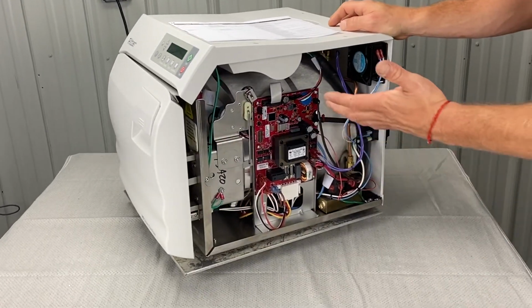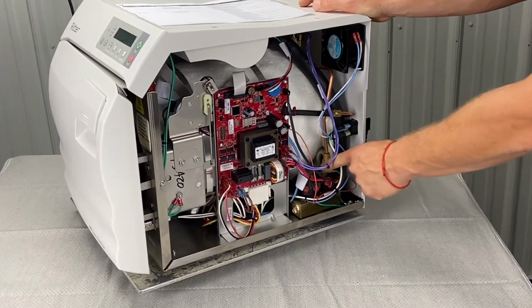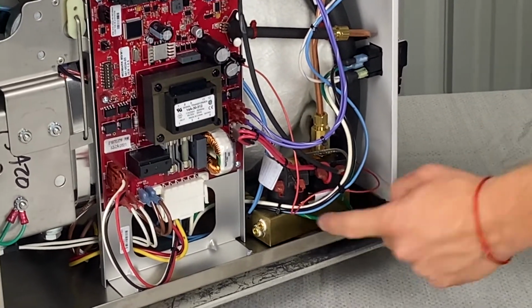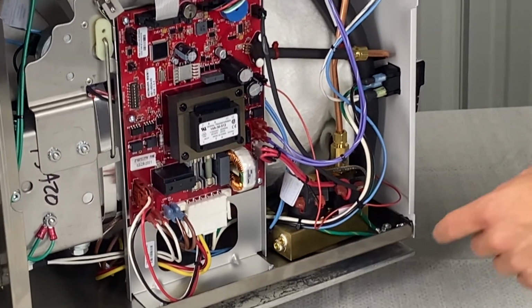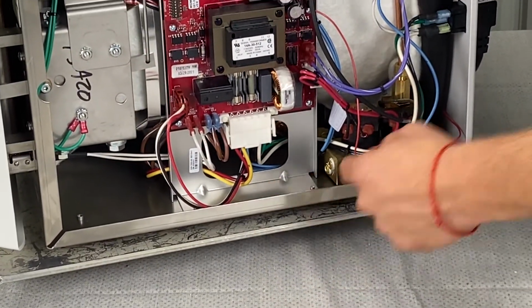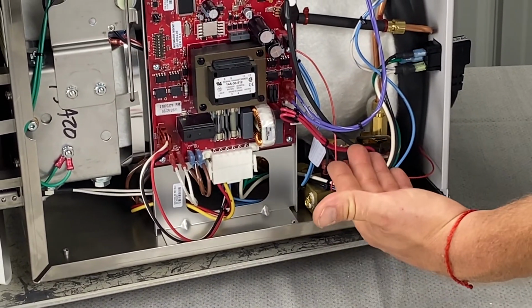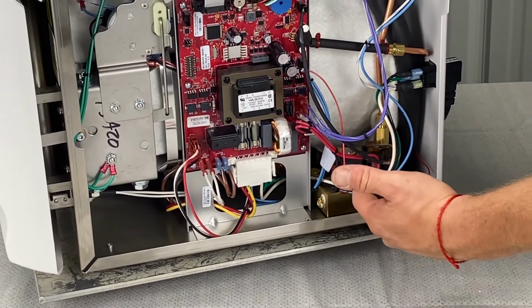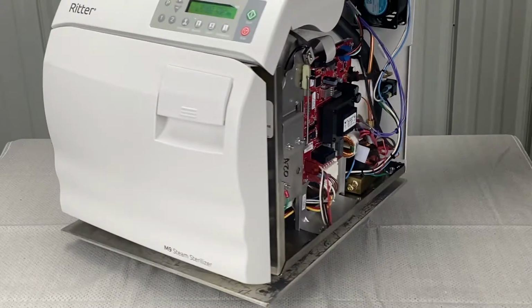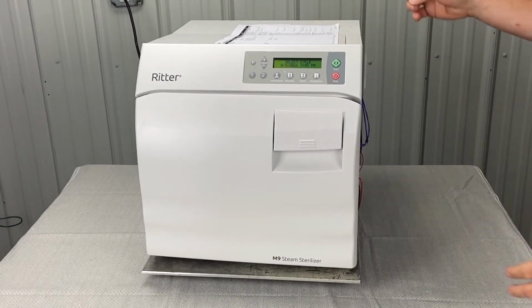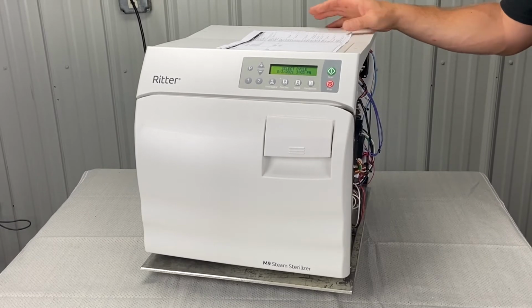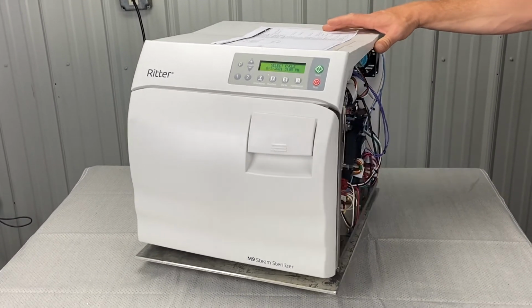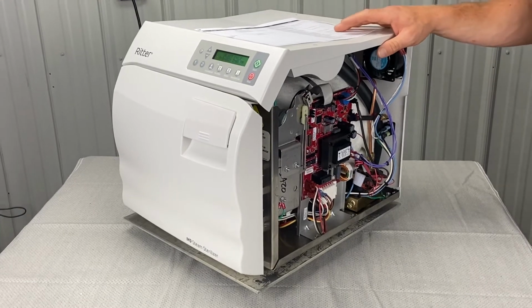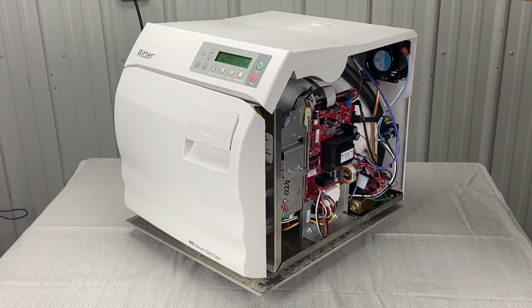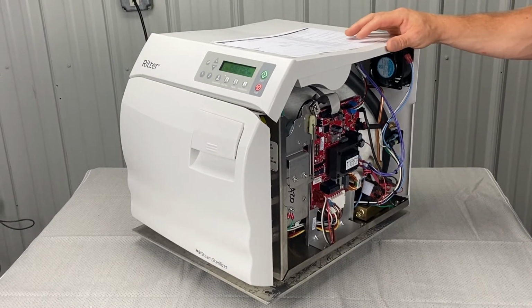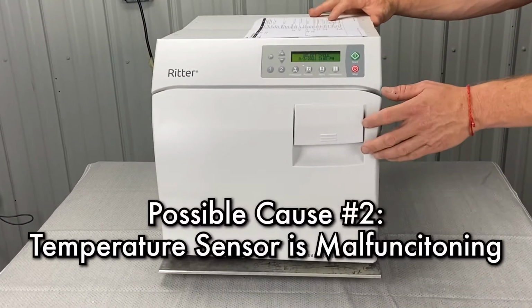So it's really nice, like I said, to run this with the cover off, because now we can inspect these valves. You might see leaks come out from underneath here where they screw it to the manifold. You can look underneath. You might see leaking coming from the heating element area. There's gaskets there that go bad over time. There's plumbing under there that goes bad over time, or loosens up as this thing gets hot and vents and whatever. So you're going to check all the fittings, tighten or replace the fittings if necessary. Usually you can just throw whatever size wrench on it, tighten it up a little bit, and it'll close it off. Okay, and then from there, it could be the temperature sensor is malfunctioning.